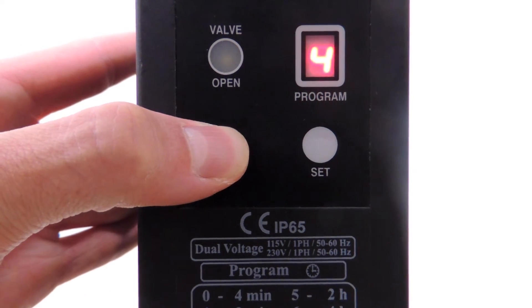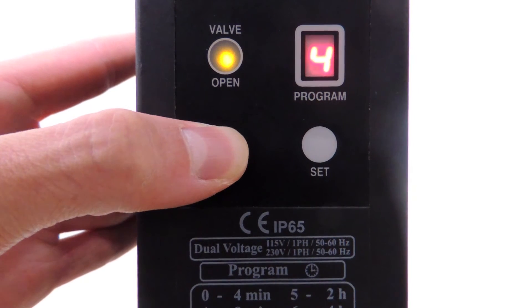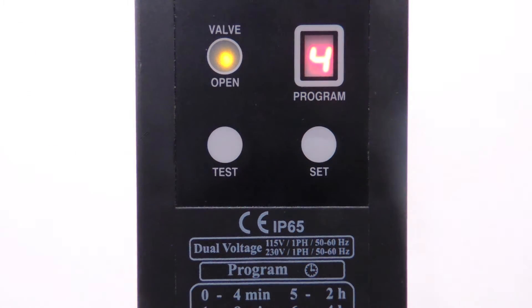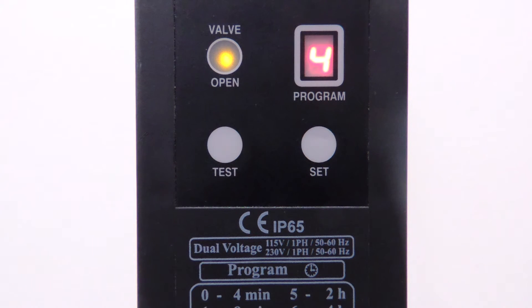Hold Test to start the purge cycle and check that the valve opens for the correct amount of time. It should be lit for 30 seconds, and then turn off on its own.